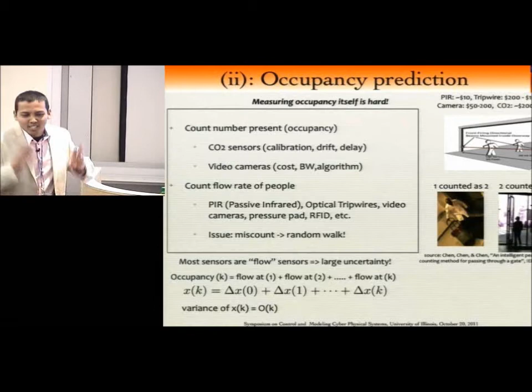People will try to sell you sensors that supposedly measure occupancy — they don't. Some sensors are used for demand control ventilation, like CO2 sensors, which measure CO2 level and adjust air supply flow based on that. It works for big auditoriums or movie theaters, but not for small rooms. I'll talk about that in a moment, but one problem with these is they drift out of calibration very frequently — they're highly sensitive.